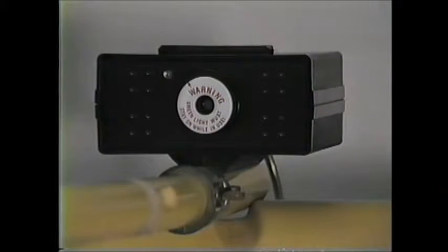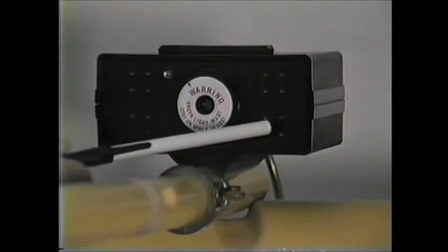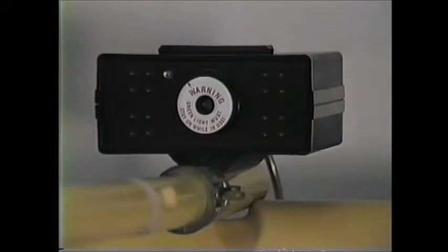When the unit is first switched on, all lights and the audio alarm should come on. This is a built-in test feature. One at a time, the lights will extinguish, starting first with the 11,000 volt bank, then the 7,000, 2,000, and finally the 600 volt bank. When the 600 volt bank goes out, the audio alarm will also go out. Only the green power light will remain on.